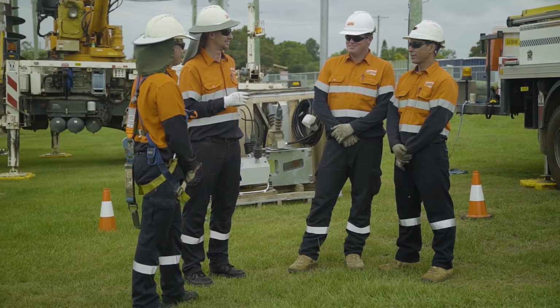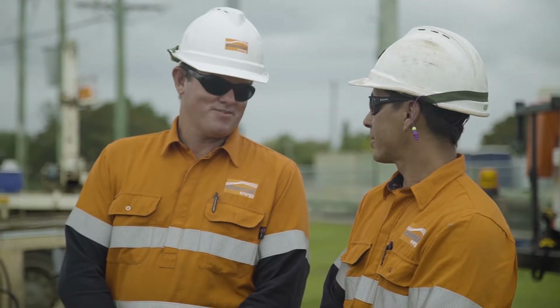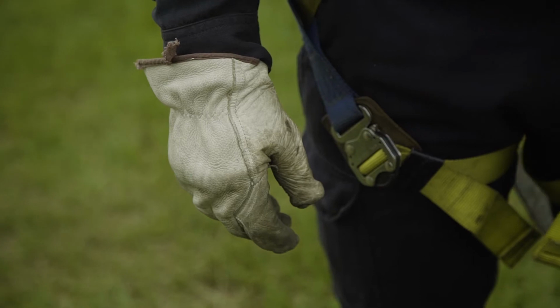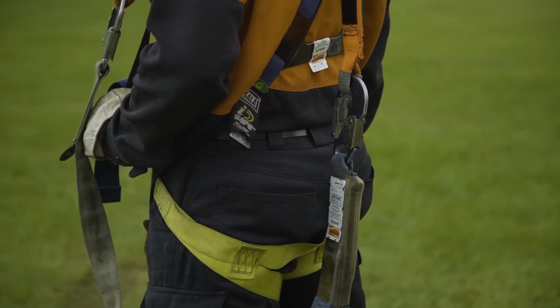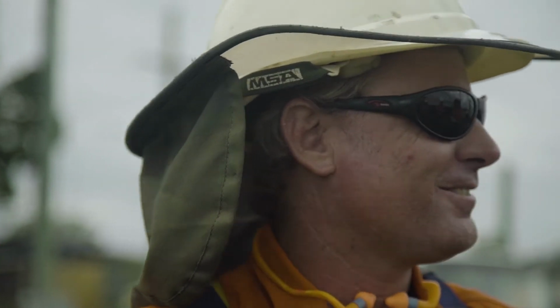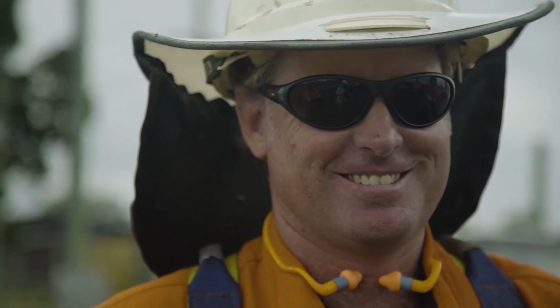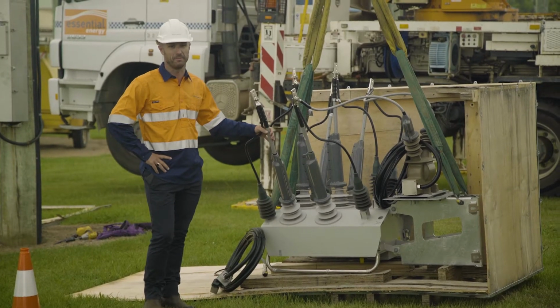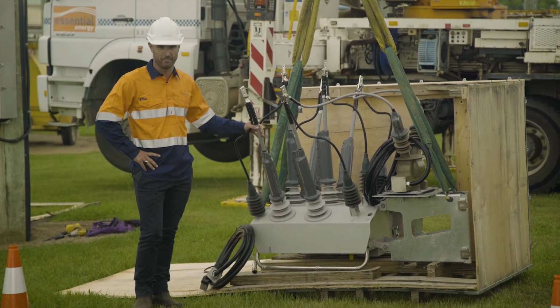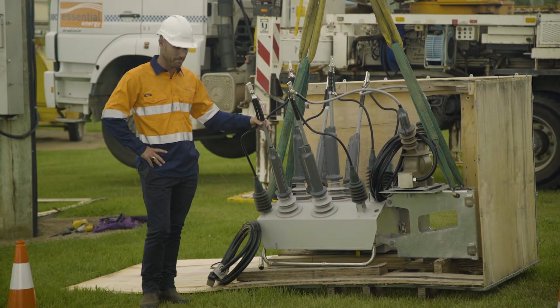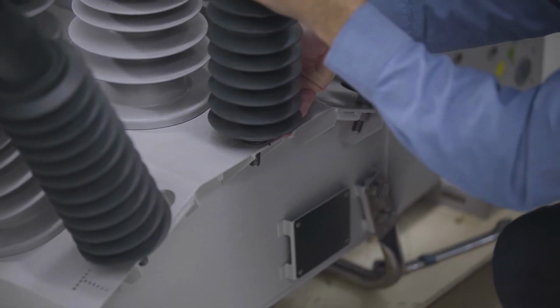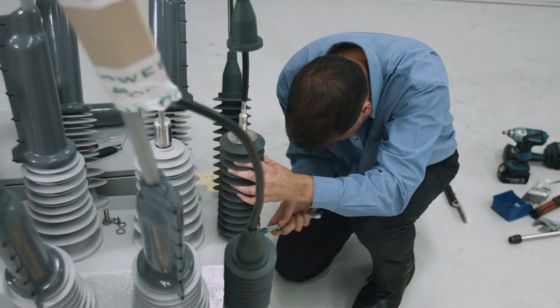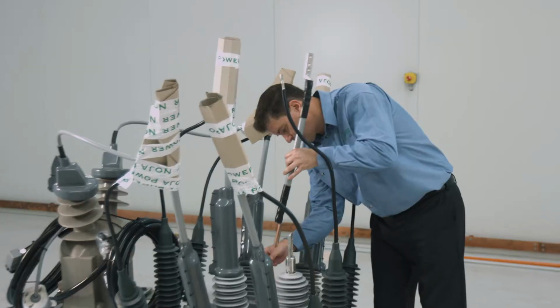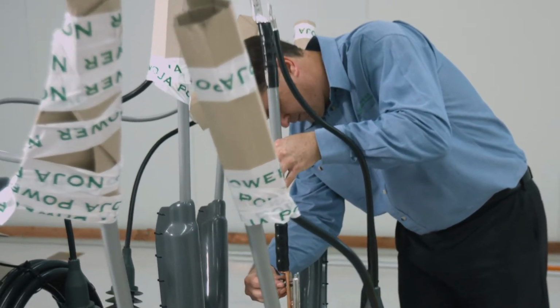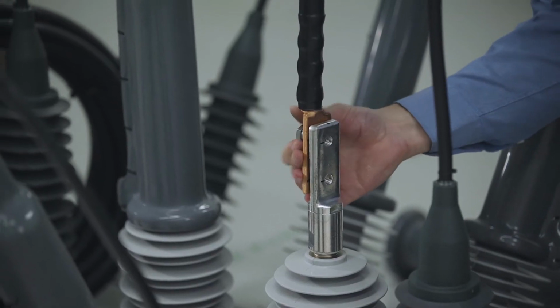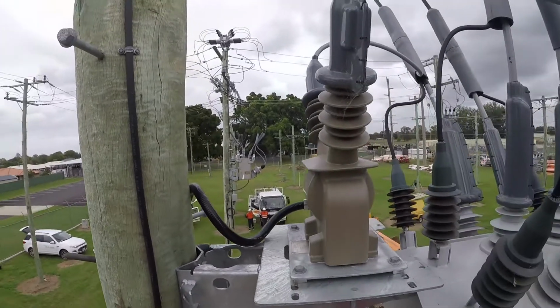Using the correct personal protective equipment is imperative for safe installation of electrical equipment. Essential Energy follows industry best practice, and its number one priority is the safety of its employees. NOJA Power recommends that all accessories be fitted to the switch before it is lifted up a pole. In this instance, that's now been completed. We've had the surge arresters fitted, the HV tails, and the VT.